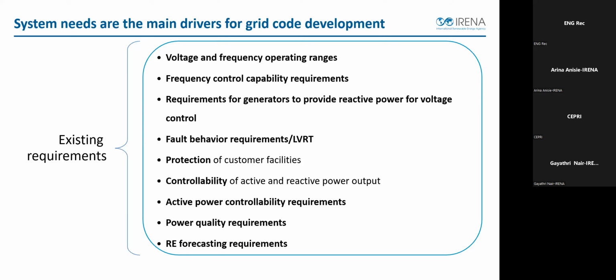Then controllability for active power and reactive power has been predominantly seen in transmission connected VRE systems enabled via SCADA system, where you can actually change the set points remotely. Fault behavior is another common parameter, or variable, that is being specified in some of the grid codes, and this ensures resilience to grid faults. Protection, so that the power plant is not overprotected. And then, of course, power quality requirements, so that strict limitations can be imposed on limiting the total harmonic distortion. And VRE generation forecasting is also becoming essential, as we can already see from the example that was given by the previous speaker, that it is already there in China.